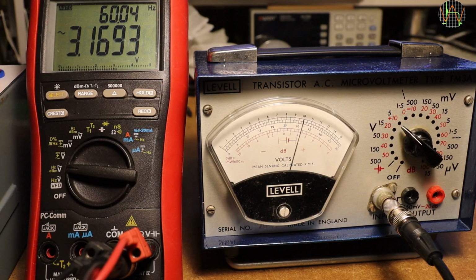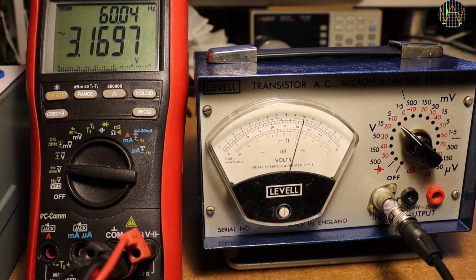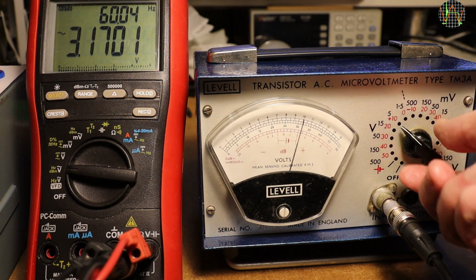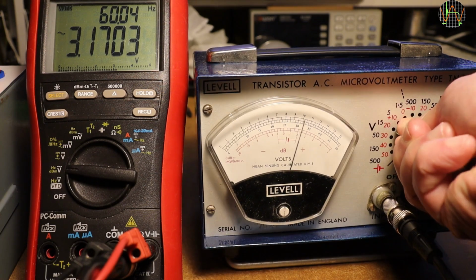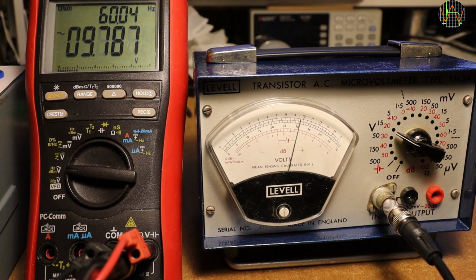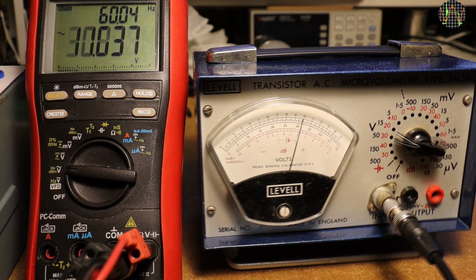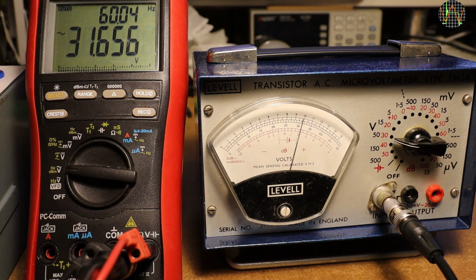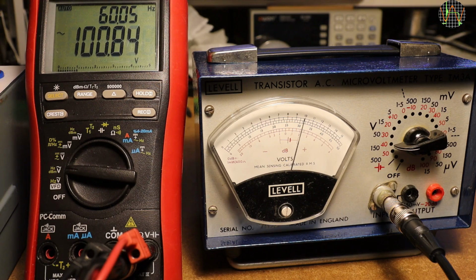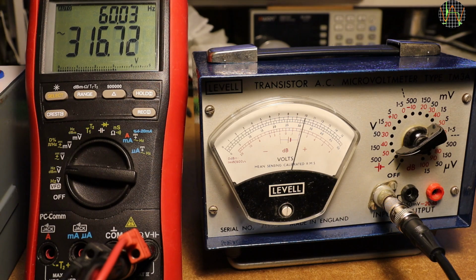Pretty impressive. Now for the higher voltages, starting at 3.16 volts at 60 Hz in the 5 volt range. I'm trying to maintain the same stepping, although I don't have the convenience of a 10 dB step attenuator now. 10 volts in the 15 volt range, 31.6 volts in the 50 volt range, 100 volts in the 150 volt range, 316 volts in the 500 volt range. All reasonably accurate, and for this being a relatively simple meter, pretty good.